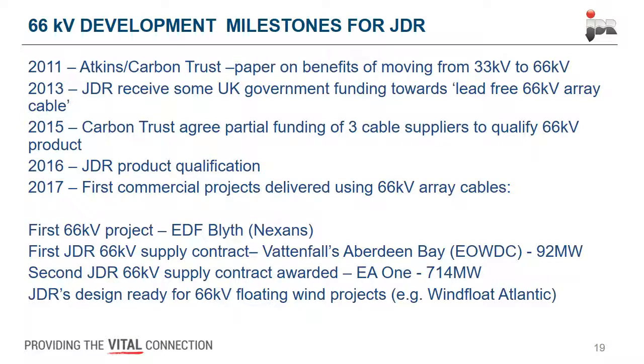So this doesn't happen overnight. It was originally proposed by an Atkins Carbon Trust study in 2011. In 2013, we received some government funding to look at lead-free 66 kV array cables. And in 2015, the Carbon Trust, together with some of the offshore utilities, partially funded 3 cable suppliers to qualify product. We did our qualification in 2016, and the first commercial projects were delivered in 2017. Nexans were actually the first to deliver one for the EDF Blyth project. We were second with supplying to Vattenfall, and then those are both demonstration projects, but then the first really big project to embrace 66 kV has been East Anglia 1, a 714 megawatt project, which JDR secured, and we're currently manufacturing that now.